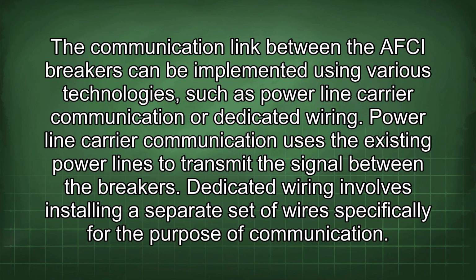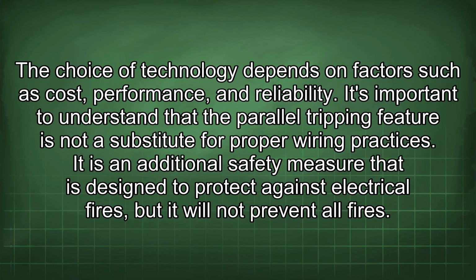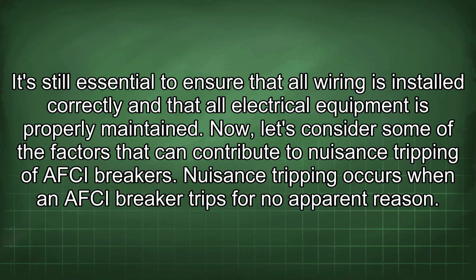The communication link between the AFCI breakers can be implemented using various technologies, such as power line carrier communication or dedicated wiring. Power line carrier communication uses the existing power lines to transmit the signal between the breakers. Dedicated wiring involves installing a separate set of wires specifically for the purpose of communication. The choice of technology depends on factors such as cost, performance, and reliability. It's important to understand that the parallel tripping feature is not a substitute for proper wiring practices. It is an additional safety measure that is designed to protect against electrical fires, but it will not prevent all fires. It's still essential to ensure that all wiring is installed correctly and that all electrical equipment is properly maintained.